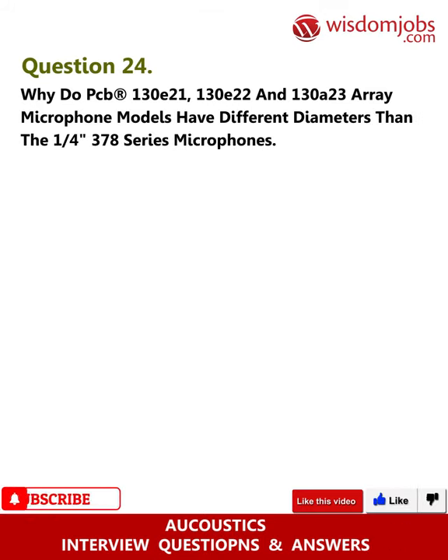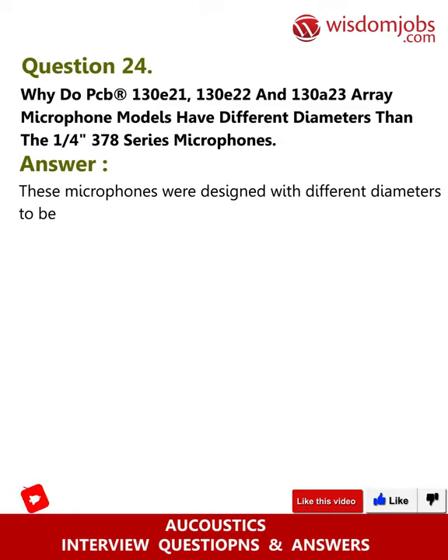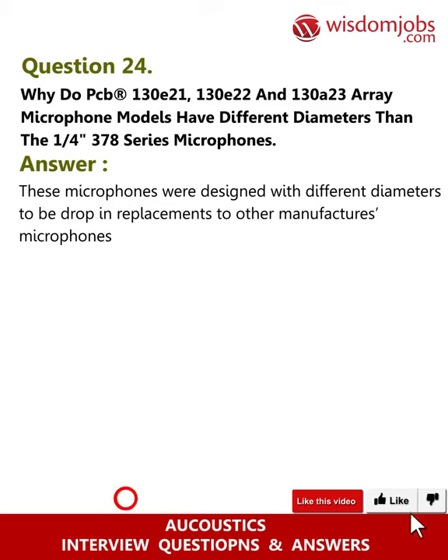Question 24: Why do PCB 130E21, 130E22, and 130A23 array microphone models have different diameters than the one-quarter-inch 378 series microphones? Answer: These microphones were designed with different diameters to be drop-in replacements for other manufacturers' microphones. This eliminates the need to change holders or change the setup.